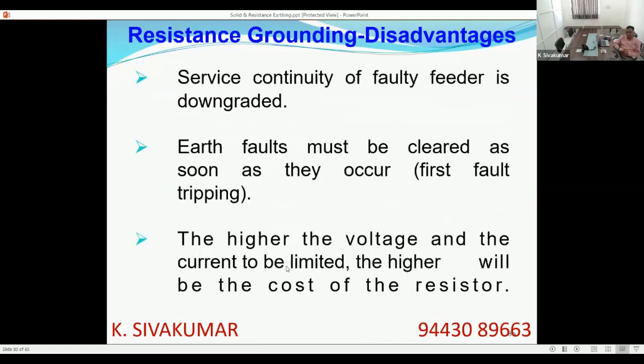Disadvantages: in a low resistance grounded system, or a high resistance grounded system with a very sensitive earth fault relay or a neutral displacement relay, service continuity of the faulted feeder is downgraded. That means the faulted feeder gets tripped, compared to an ungrounded system. Earth fault must be cleared as soon as it occurs. Otherwise, the same disadvantage, because the ground always rises to the faulted phase. The higher the voltage and the lower the value of earth fault current to be limited, the higher will be the cost of the resistor. Ohmic value increases, voltage grade increases, so the cost will be more.